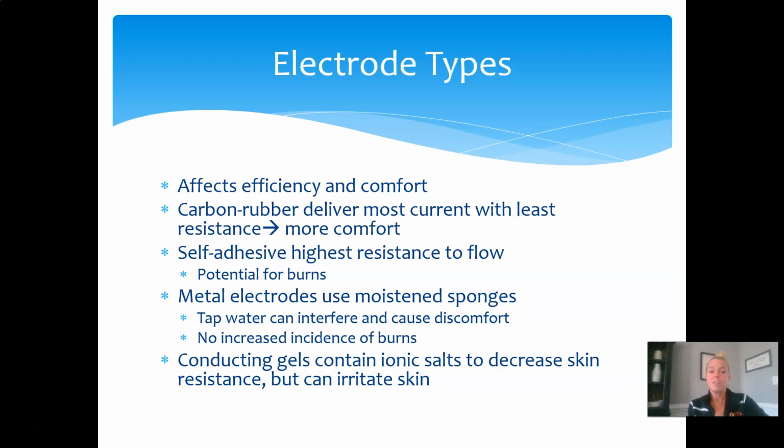The type of electrode is going to affect the efficiency and the comfort. Carbon rubber deliver a lot of current with the least resistance. Those are typically considered the most comfortable. Self-adhesive do have some resistance to flow. There is some potential for burns.